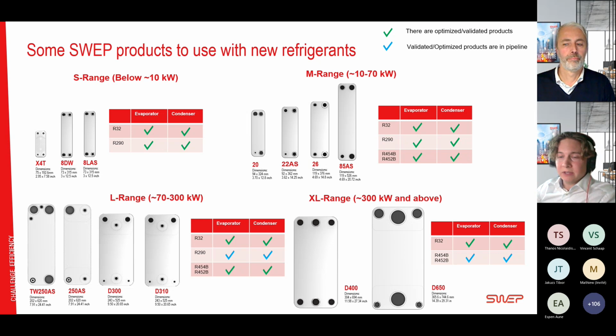Then we have the medium range, which ranges from approximately 10 to 70 kilowatts. And here we have typically residential heat pumps and also chillers. For the heat pumps, normally condensers, and for the chillers, normally evaporators. But depending on the setup, it could be both, obviously, if they're reversible or water-cooled or air-cooled. And this is a popular range where SWEP is doing a lot of refrigerant activities. We have a good coverage of R32, R454B, and propane for this range.